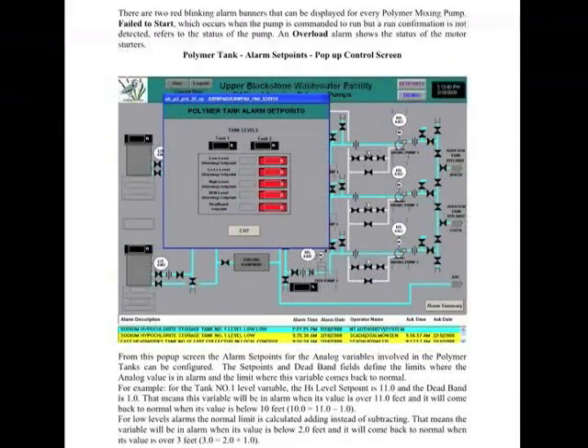Now on page 20, we're going into, again, the tank level alarms. Now there's two polymer tanks. They are sharing their alarms. There's not individual alarms for each tank. It's one set of alarms that will be applied to both tanks. So we're showing the low level set point, the low low set point, the high and the high high.